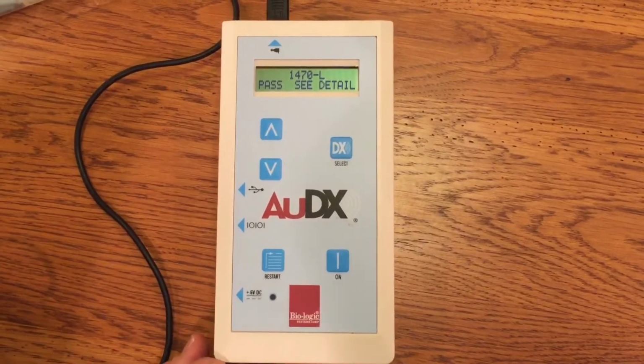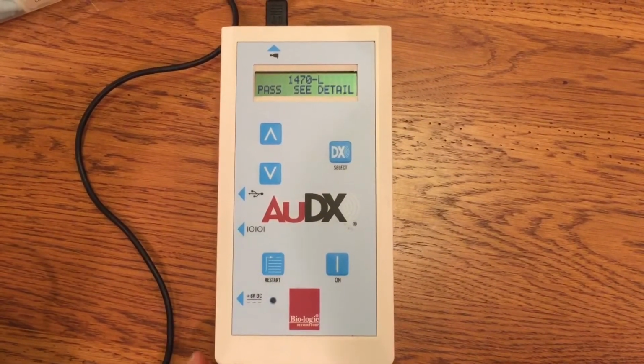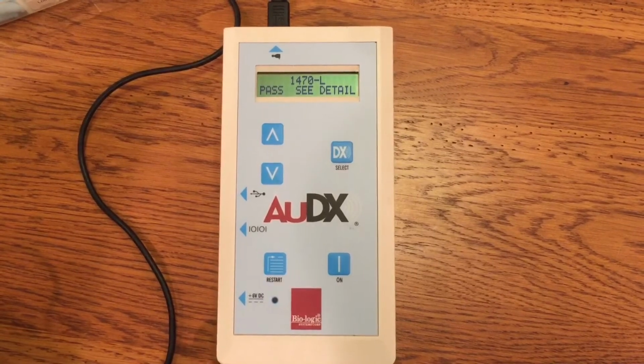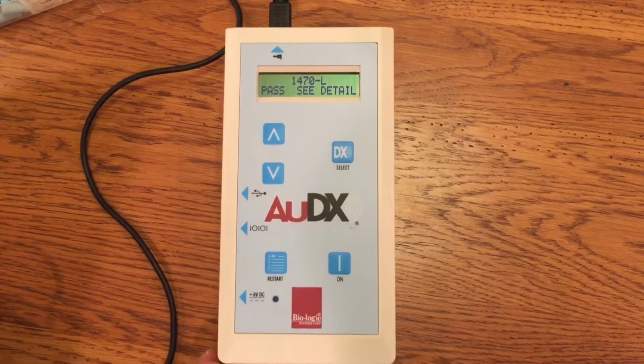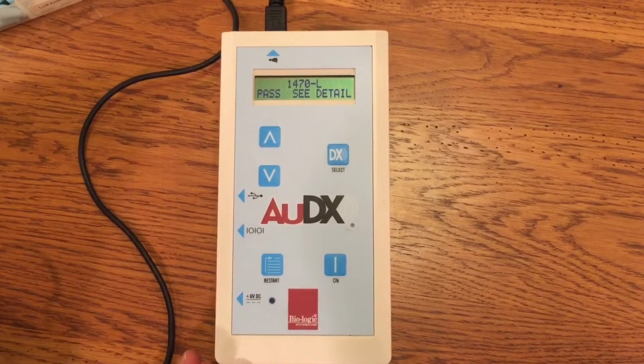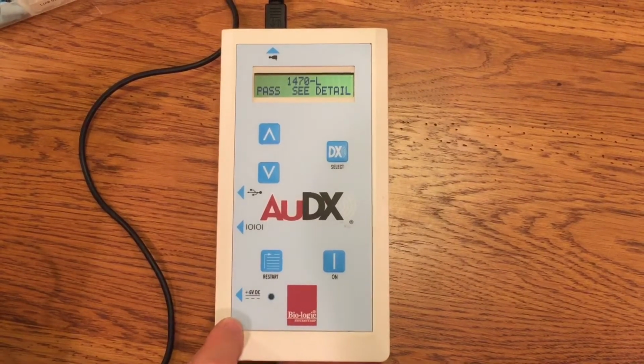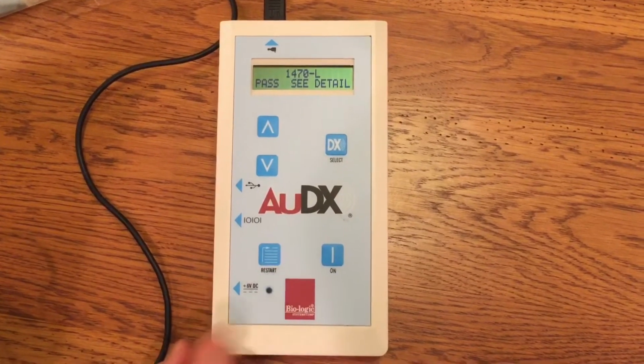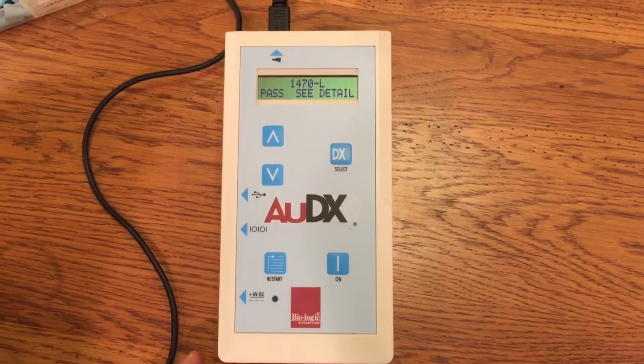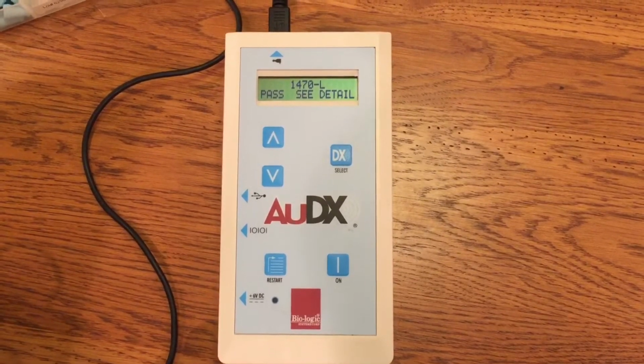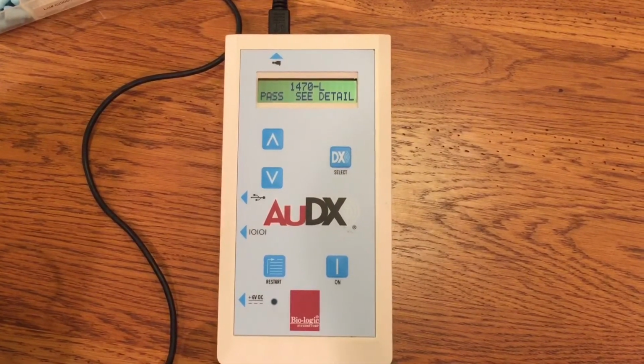In regards to screening children with PE tubes, some equipment needs an adjustment in order to screen a child with known PE tubes accurately. There is no need to do that with the AUDX. No adjustments to make, just screen as you normally would. And remember, you should expect a pass if the ears are clear and the PE tubes are functioning.